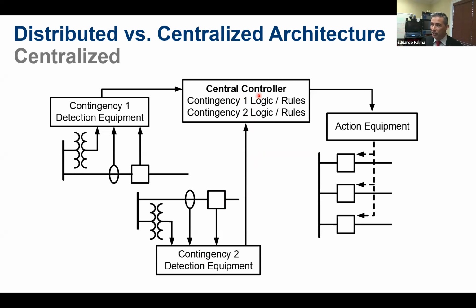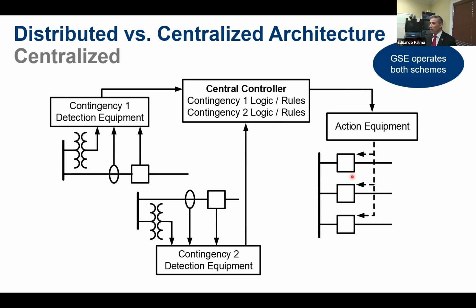The central controller can make better decisions that allow for the system to be better, because it's not shedding an amount of load that is a little bit more than needed. It's precisely the total load that needs to be shed. So it's more selective. It's better that way. So the actions are put into a matrix in which the controller understands, based on the power system conditions that are being reported very, very quickly in millisecond time into the controller, how to react. And the reaction will be sent via communications channels in order to shed loads and maintain this balance that we need. Both systems, the distributed and the central system, operate in GSE.